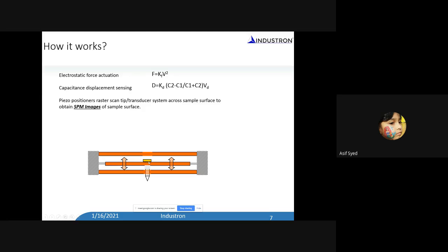Now, if you put a tip into the center plate, and the tip is in contact with the specimen, then you can apply the force onto the sample and measure the displacement. To measure the displacement, we measure the capacitance between these parallel plates. You know that when you have a parallel plate and an air gap, there is a capacitance. So when the center plate moves in between these two outer plates, the gap is changing. Because the gap is changing, the capacitance is going to change. And if you have a way of measuring the change in capacitance, you can measure the displacement. So with this simple concept, we can apply force and measure displacement.